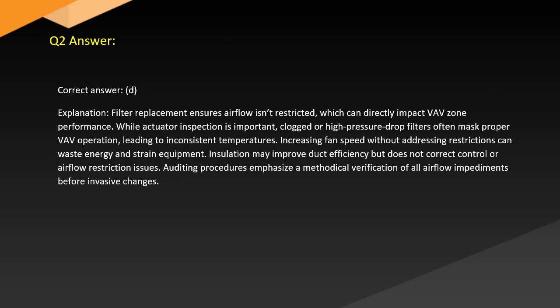Answer. Correct answer: D. Explanation. Filter replacement ensures airflow isn't restricted, which can directly impact VAV zone performance, while actuator inspection is important. Clogged or high-pressure-drop filters often mask proper VAV operation, leading to inconsistent temperatures. Increasing fan speed without addressing restrictions can waste energy and strain equipment. Insulation may improve duct efficiency but does not correct control or airflow restriction issues. Auditing procedures emphasize methodical verification of all airflow impediments before invasive changes.